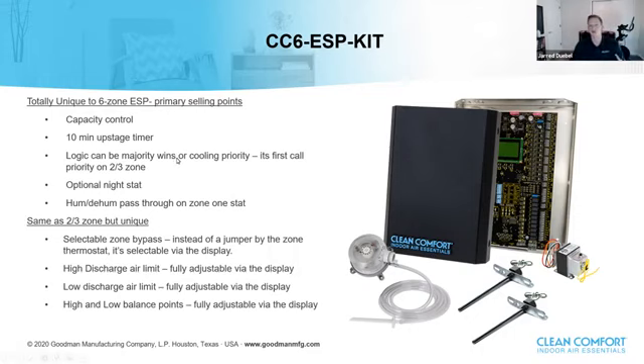The logic in the 6-zone panel changes a little bit. When we're talking about our 2 to 3 zone panels, we have first call priority, which means if a heating call comes in and then 5 seconds later a cooling call comes in, we're going to take care of that heating call that came in first, then we're going to go over to the cooling call. Well, we can change that with the 6-zone panel. First of all, we do a voting system, or majority wins, when it's set to its standard mode. That means if you get 3 heating calls and 2 cooling calls, we're going to take care of heating first.